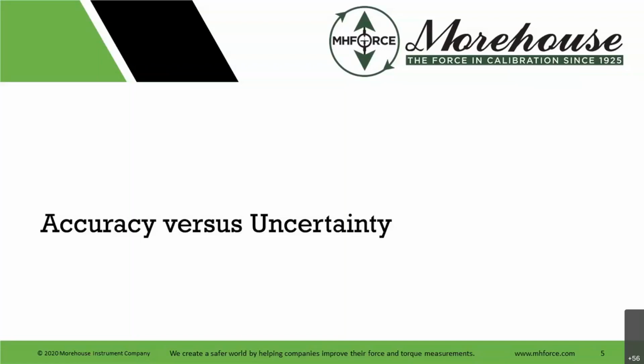A lot of people confuse accuracy with uncertainty. This happens quite a bit. Well, how accurate is this device? Or you see a specification, or the auditors go out, you audit some labs, and they're using accuracy in place of uncertainty. They're saying, hey, I sent this to Morehouse. I asked for this to be 0.1% of applied. Morehouse told me it was 0.1% of applied. They used the method 5 from ANSI Z540.3 handbook, and I'm good. That's what I'm going to state on my certificate. That's what I'm going to state on my scope, right? Someone signs off on it. Okay, all good. Where's the stability? Where's all the other things that go into this? An accuracy statement alone is not to be substituted in lieu of uncertainty.